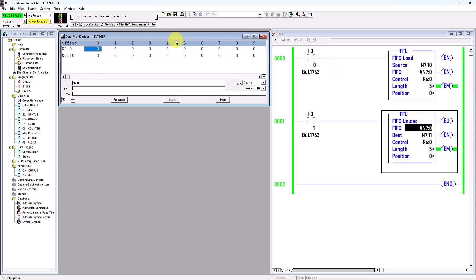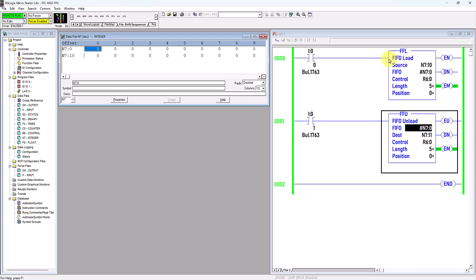In other words, this FFL or First In First Out Load instruction, when energized, will cause the value from N7:10 to load into the file address N7:0. This is the first to load in — that's why it's called First In. First In Load is what this means.